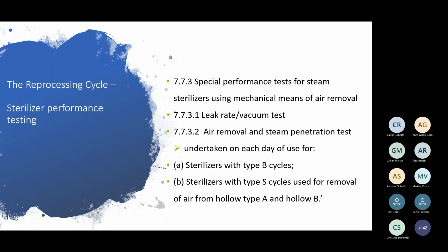So when we're looking at performance testing, special performance tests for steam sterilizers using mechanical means, this is straight out of the standard. So 7.7.3, this is the area in the standard that it's talking about. The leak rate vacuum test. So as I said before, you need to do that if your machine has a vacuum test, but you need to do a risk analysis around how often you need to do that vacuum test.